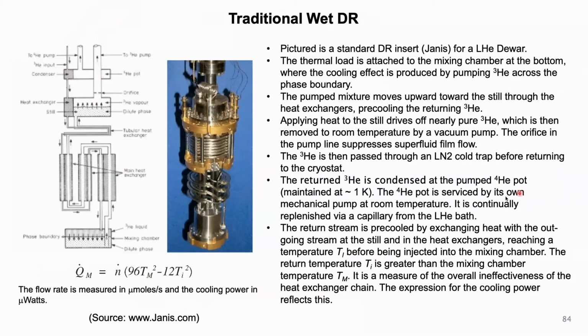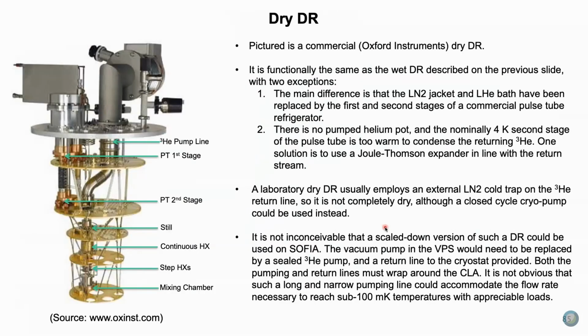That's one of the drawbacks of a warm circulation system. You have to have all very good heat exchangers. So the returned helium-3 is condensed at the pumped helium-4 pot, which is maintained at around 1 Kelvin. The helium-4 pot is serviced by its own mechanical pump. The return stream is pre-cooled by exchanging heat with the outgoing stream at the still and the heat exchangers. And it reaches a temperature Ti. I stands for in, I guess. That's the temperature at which it goes back into the mixing chamber. And that lowers the overall cooling power. So that temperature depends completely on how good these heat exchangers are.